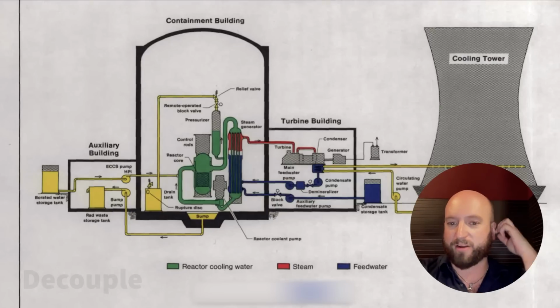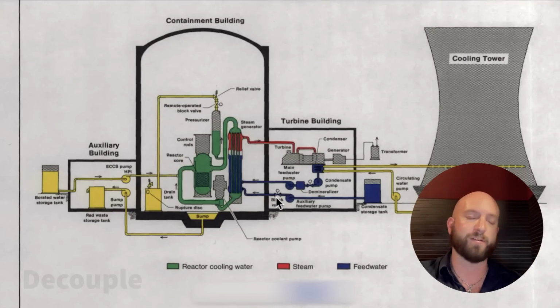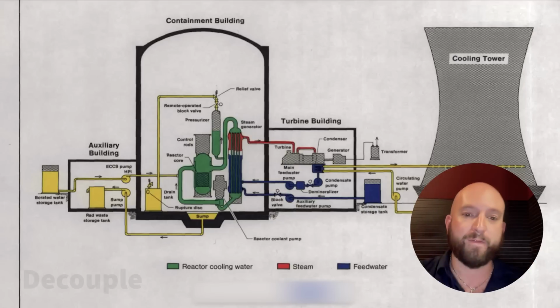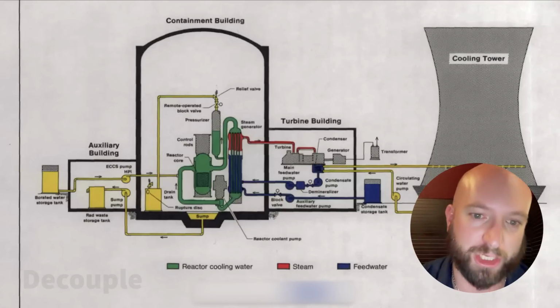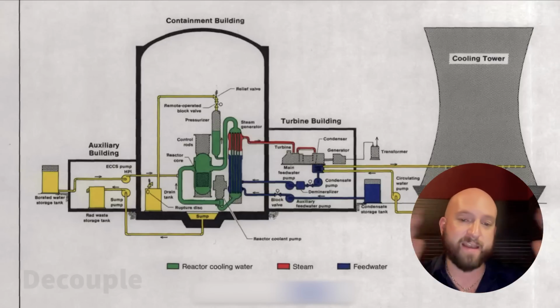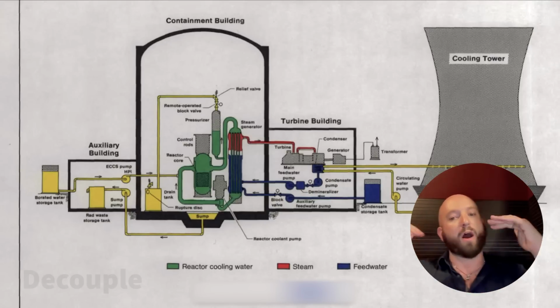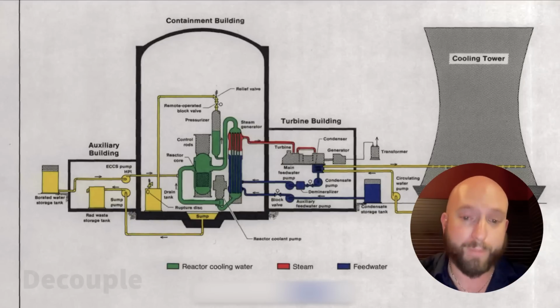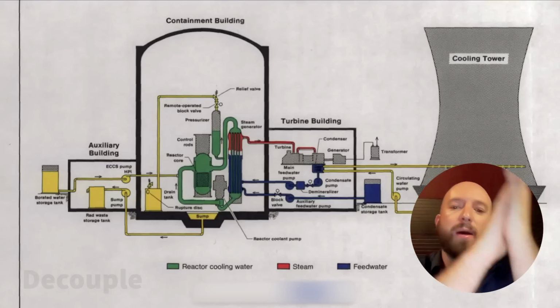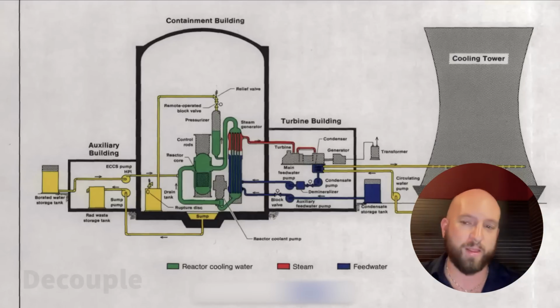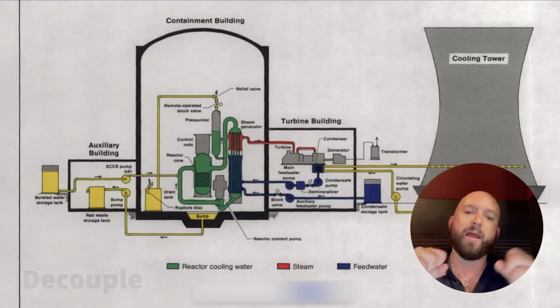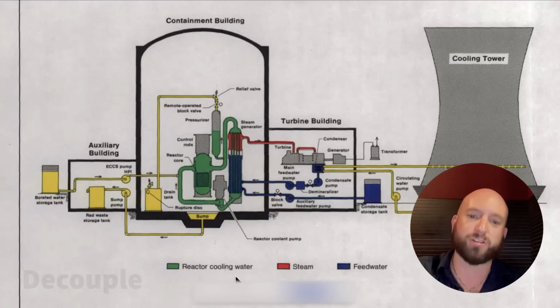Right. Now, here's where the accident really takes a turn for the worst. The first thing that the operators recognize, about 8 minutes in, is that these block valves are closed. That is a very disturbing revelation: the steam generators had boiled dry, and the auxiliary feed water pumps that they thought had been running had turned on, but were blocked by a valve. One of the operators recorded that he almost ripped open the switch on the control panel to open that block valve to let the water go back into the steam generator.